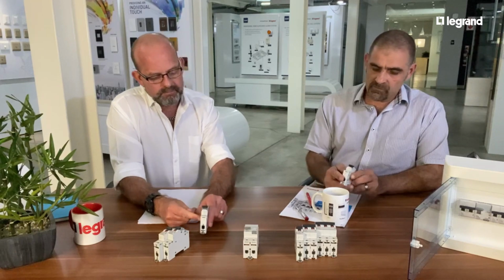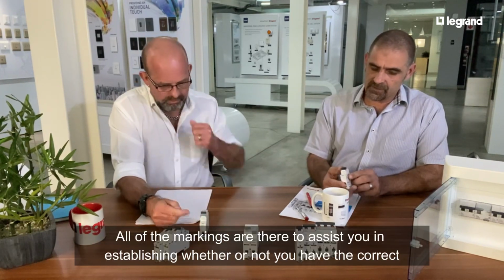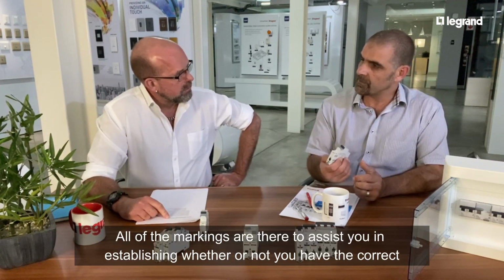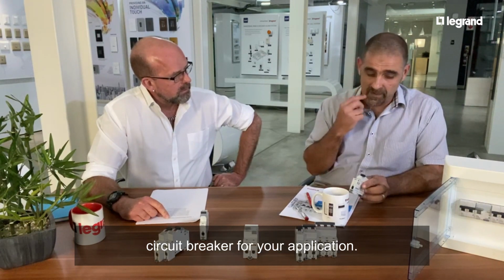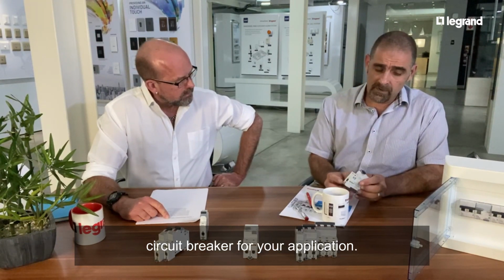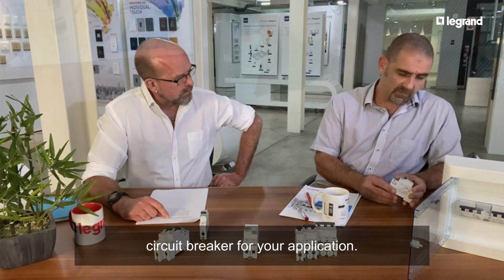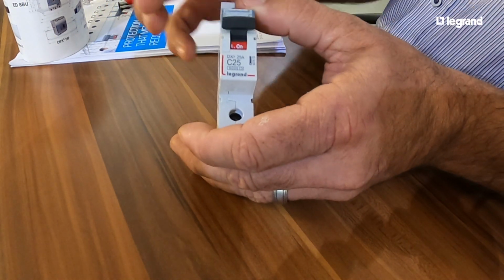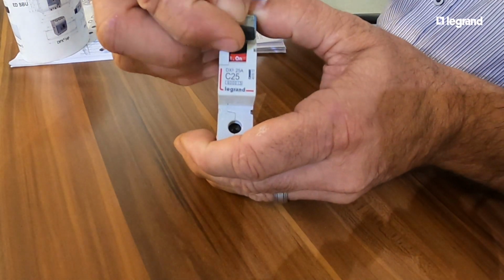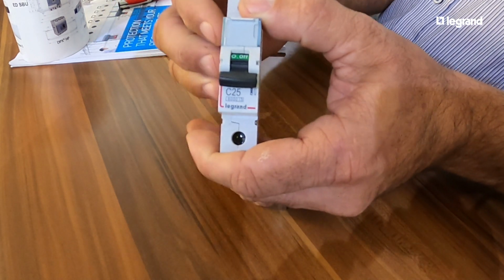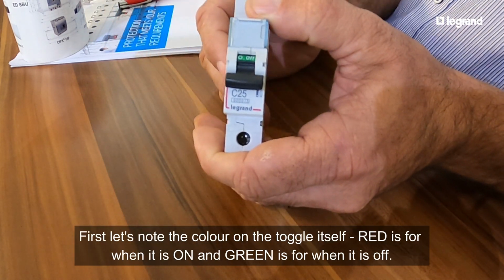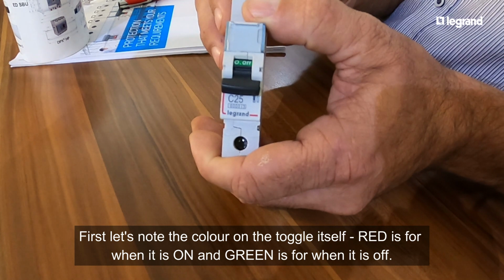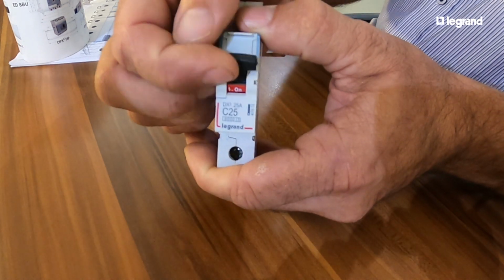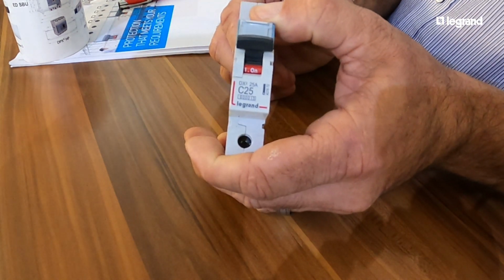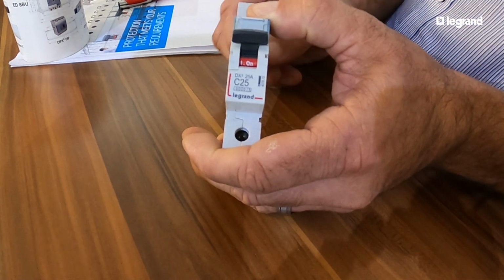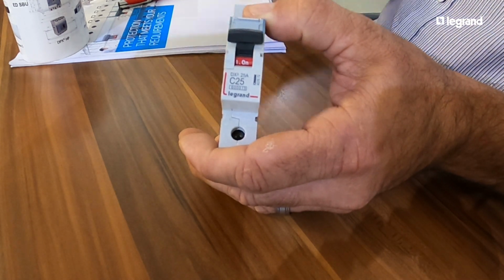Yes. All of these markings are there to assist you in establishing whether you have the correct circuit breaker for the right application. First off, you will see there's a color on the on-off toggle itself. In the off position, it goes green, giving you the indication that the power is switched off. And when it's in the up position, it gives you the red color, showing you, be careful, there's power.